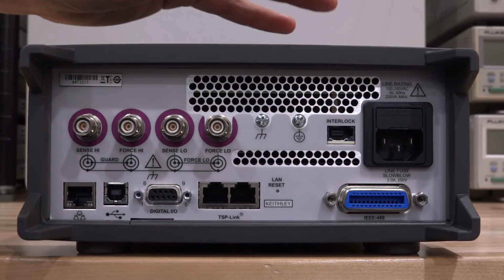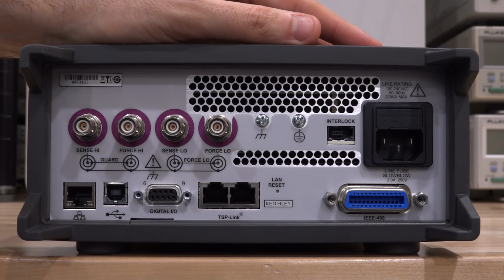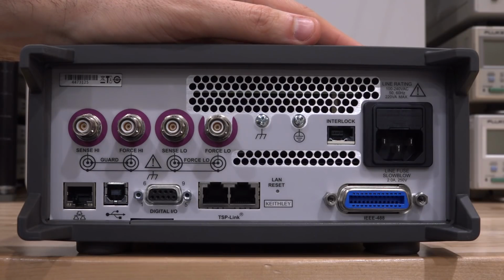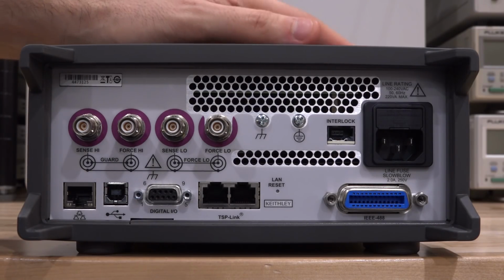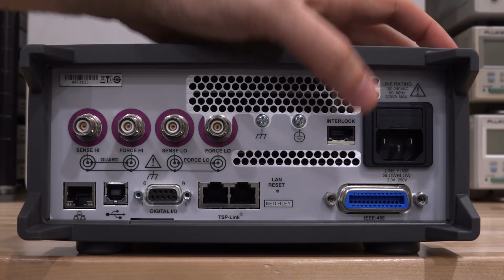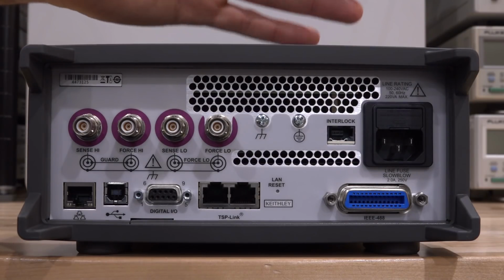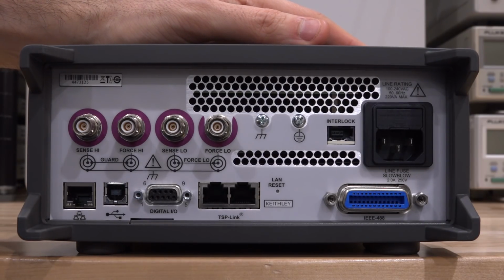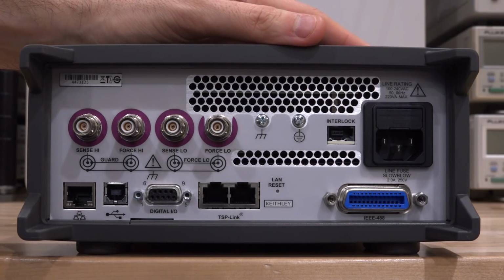Interlock is particularly important for an instrument like this, because when you go to 1000 volts, you need to have some safety in place to make sure somebody doesn't accidentally touch a setup that's live, for instance. Usually those setups are enclosed in something that trips the interlock if it's opened, and that way the output is disconnected and you don't accidentally get zapped with 1000 volts on your device under test, which is quite good, and we will see that in our setup too.